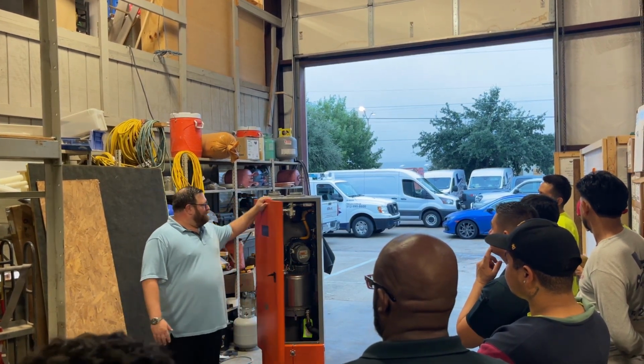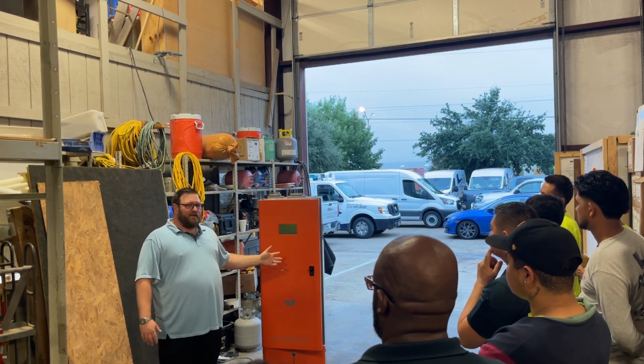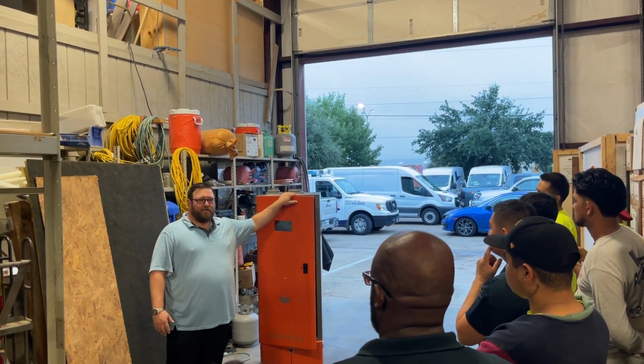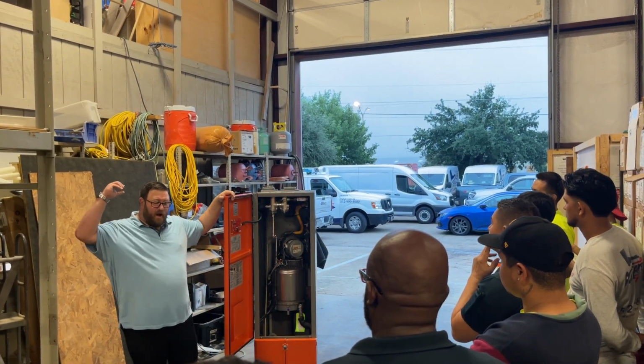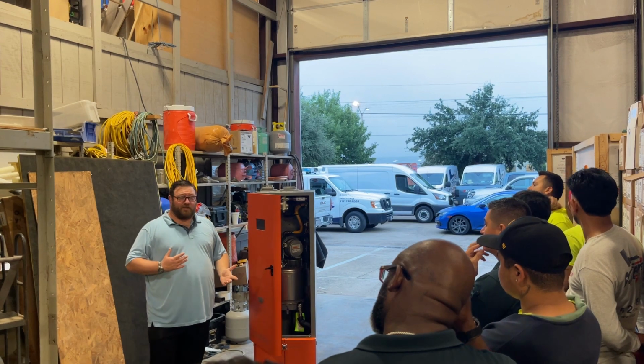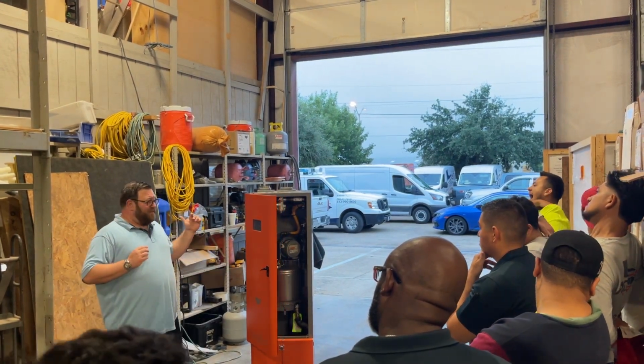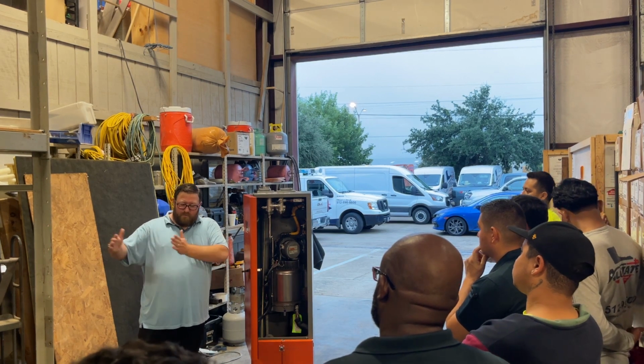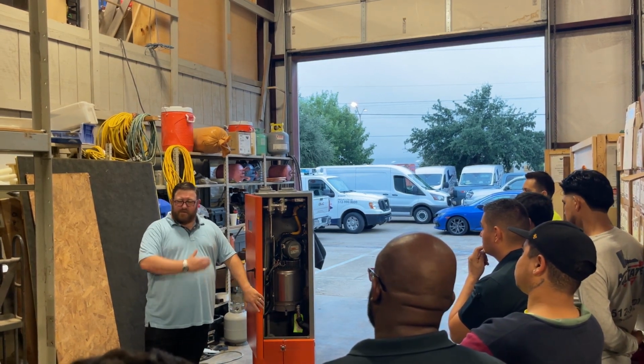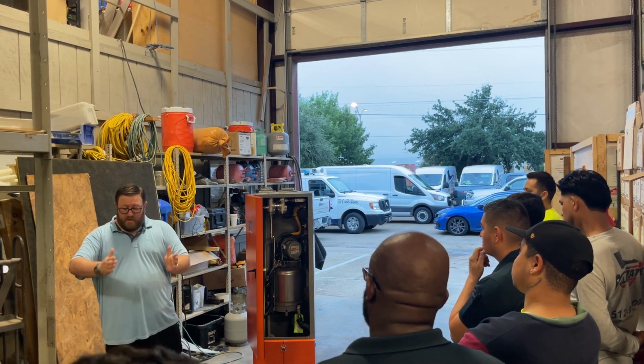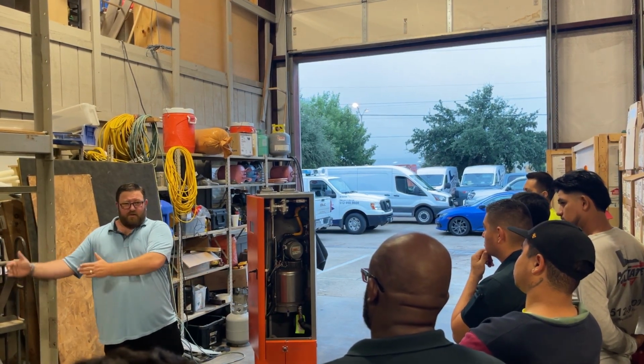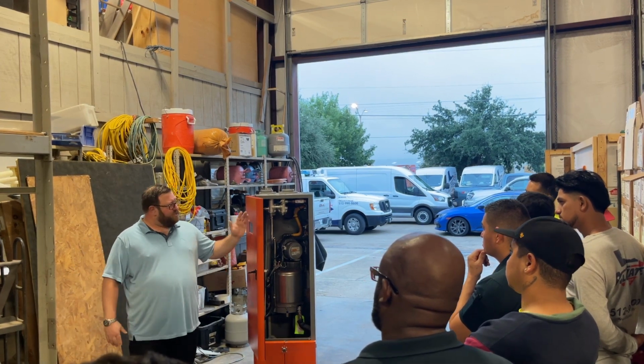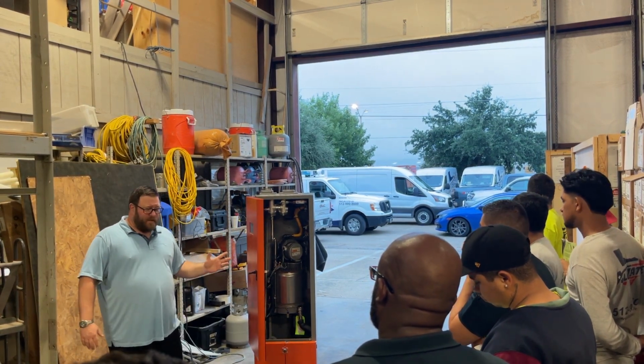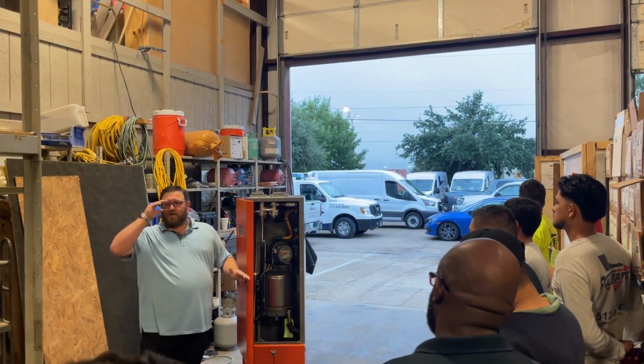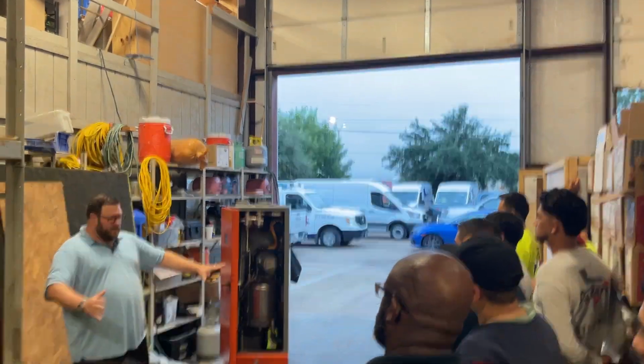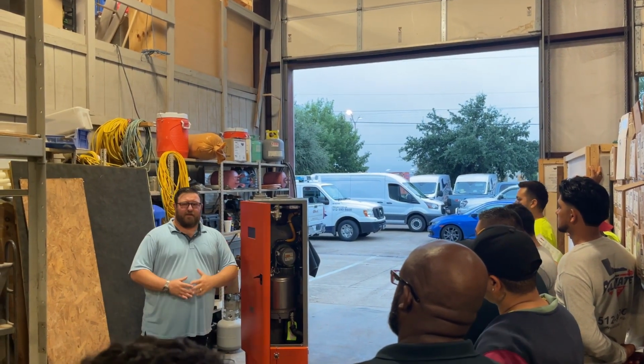You can go into the unit, and if you have 4 of these together, you can turn staging on or off. If you have a project that needs a lot of hot water fast, turn staging off — that opens all the valves and gets it ready to go. If it's a business where hot water is needed only at certain times of day, turn staging on: it'll run 70% on one heat exchanger, then kick on the next at 70%, and so on, choosing randomly to keep even use across all the heat exchangers. Whether cascaded or a single unit, it makes sure everything gets used equally.